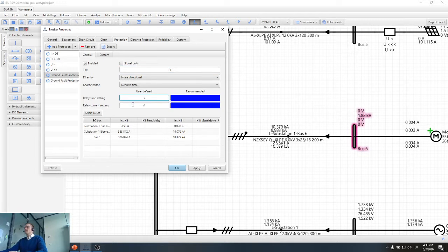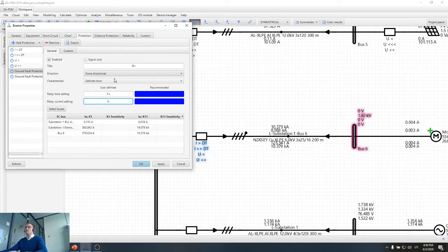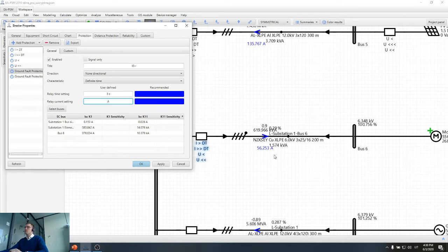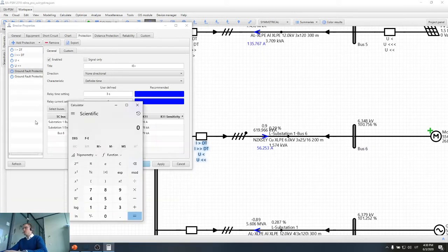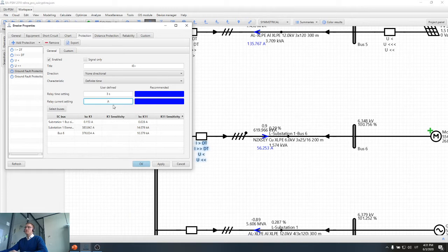And here I will set the time, let's say 3 seconds, and 3 seconds will apply in case the earth fault current is something like 5% of the nominal current. This is to avoid the protection tripping during normal operation, because earth fault protection can trip due to the error of the zero sequence transformer. The error can be around 5%, and during normal operation the zero sequence transformer measures normal current. So we can see that in case the current is more than 3 amps here, our disconnection time can be around 3 seconds. It means that there is some problem, but maybe not that big, maybe some current discharge somewhere. So we should wait for quite a long time, even 3 seconds, and not trip instantaneously.